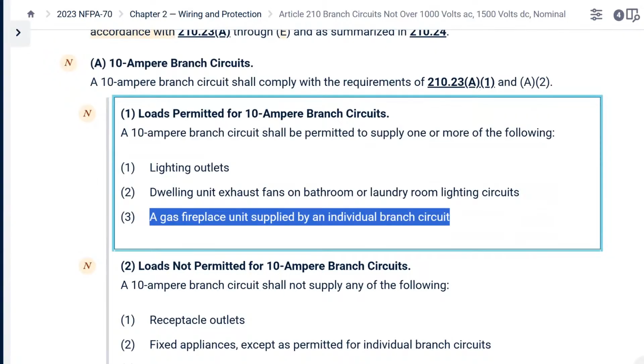So this was removed. So in the 2023 edition, the 2026 edition of the NEC, that is not going to be in there anymore. Okay, so I'll take you here. Here's your 10 amp branch circuit. So here, right here, you see that it's gone. Item number 3 is gone. So you no longer can do gas fireplace units supplied by an individual branch circuit. Can't do it anymore. All right.